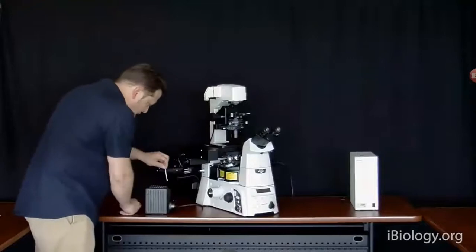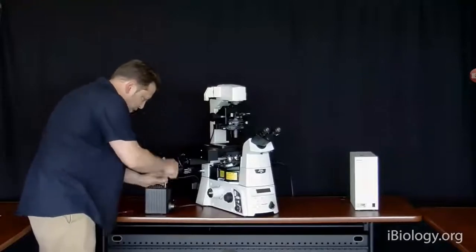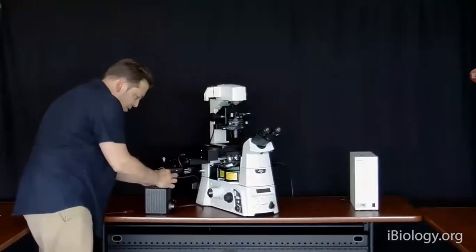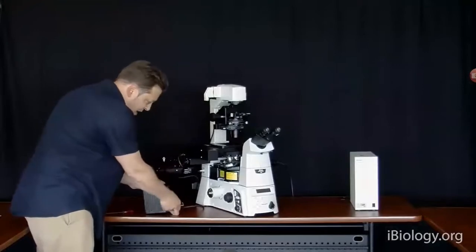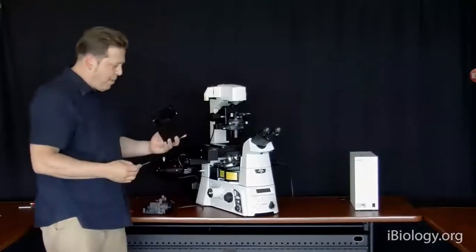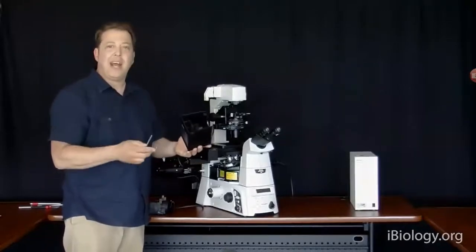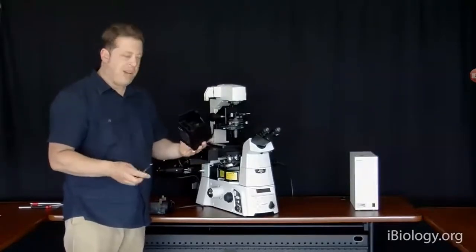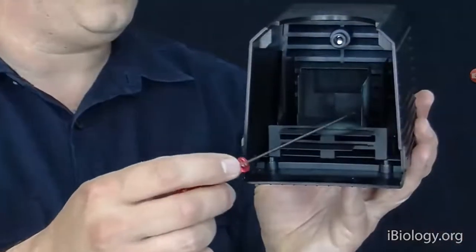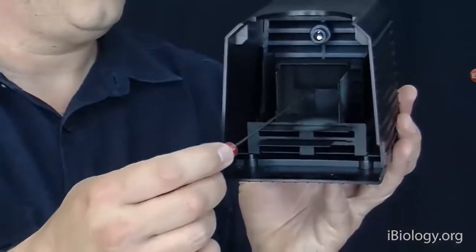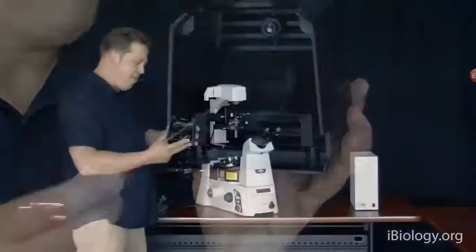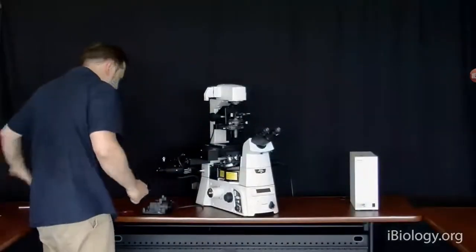If we were going to actually take that bulb out of here, we would do that by removing this insulated cover, which is very heavily shielded because the bulbs, if they have oil on them or overheat, can actually explode. It's extremely rare, but it happens. But for that, you need to have everything shielded with heavy metal inside the cover of the lamp house.